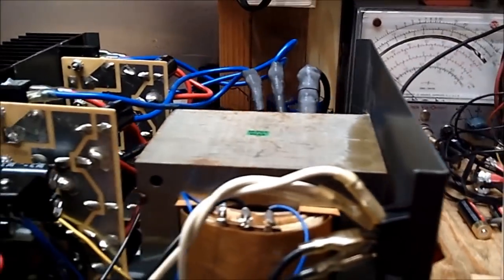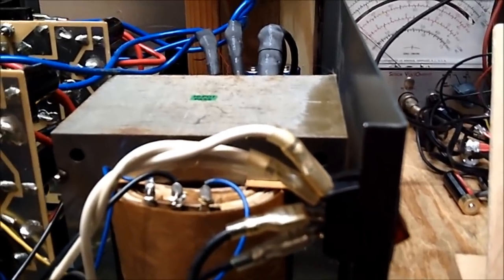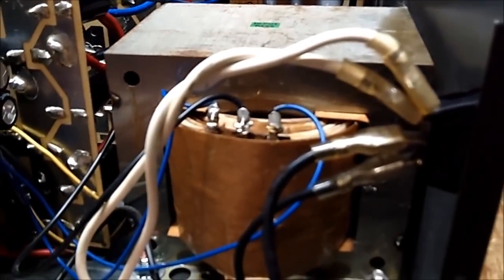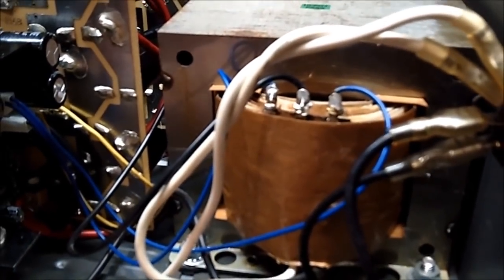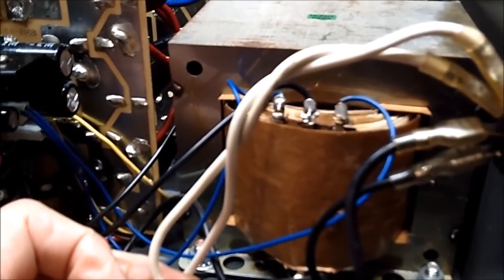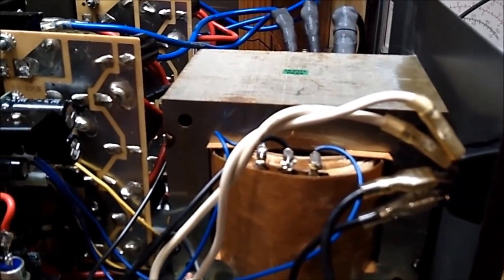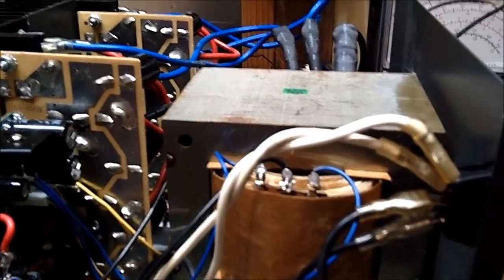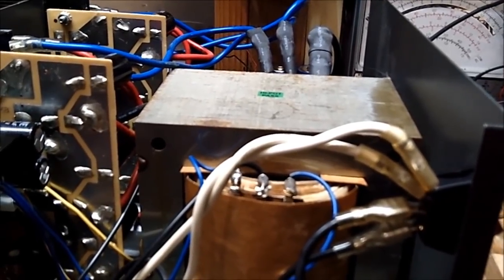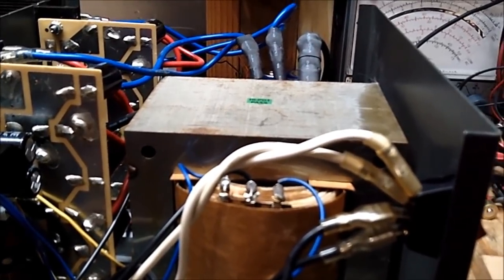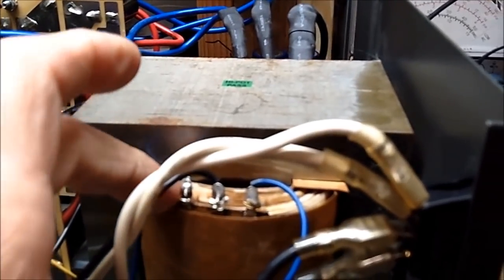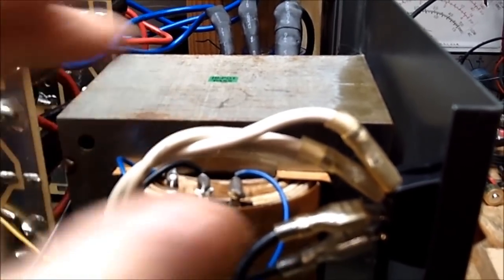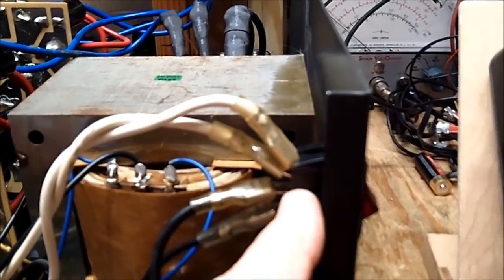So I'm getting 0.4 of an ohm DC resistance between the black wire and the white wire on the power transformer, and that would seem to indicate a short in the transformer, but there's nothing burnt, nothing smells, and the switch is open.